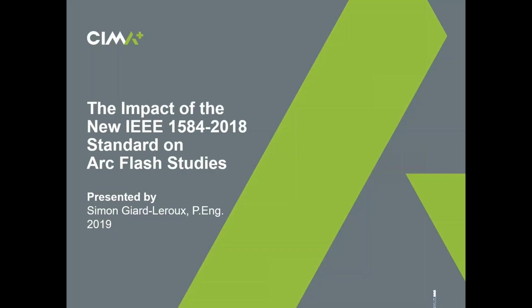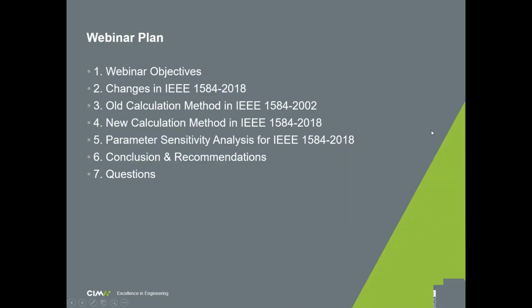So basically, the IEEE 1584 is the standard that defines the equations and the methods used for calculating arc flash energy. So this has been updated about 1 year ago, and there are many differences with regards to the older version. So the webinar today, we'll start by stating our objectives for today. Then we'll go over the changes in the new version. Then I'll show you the old calculation method in the 2002 version, and then I'll show you the new method, so you're going to be able to see the differences between both. Then I'm going to show you some parameter sensitivity analyses that we've performed for the new standard. Then we're going to end with conclusion and then a question period.